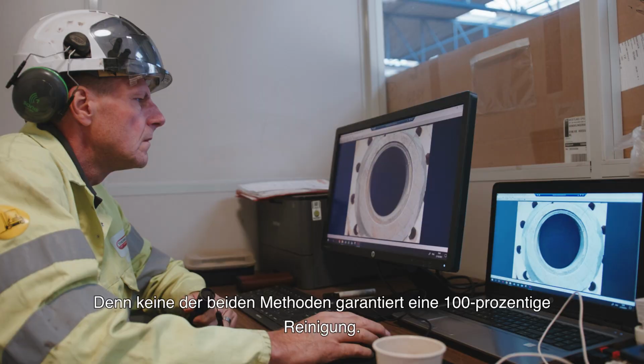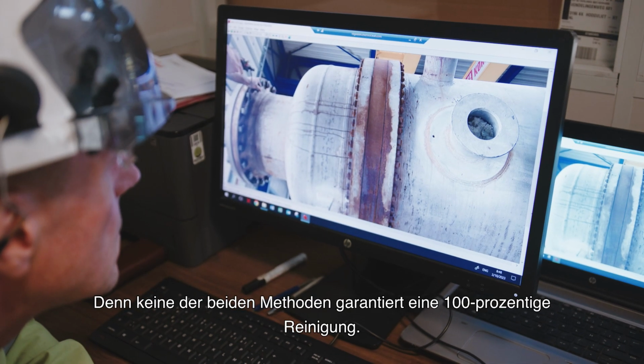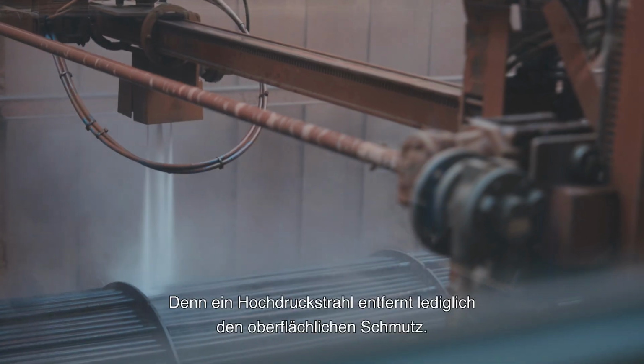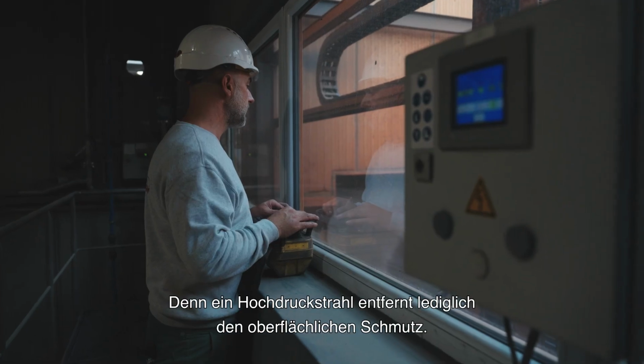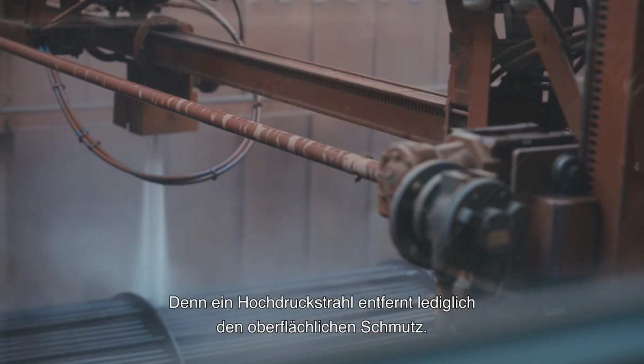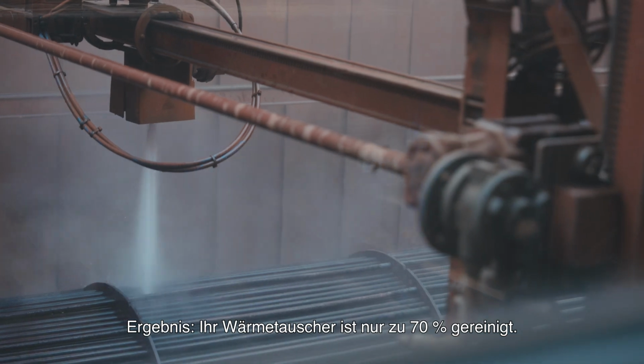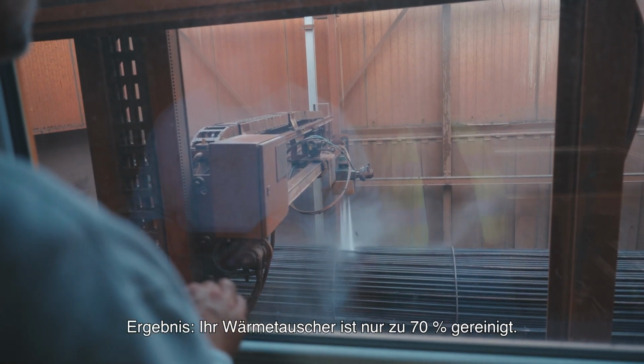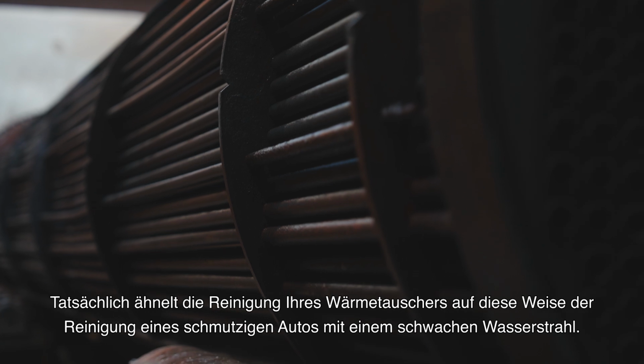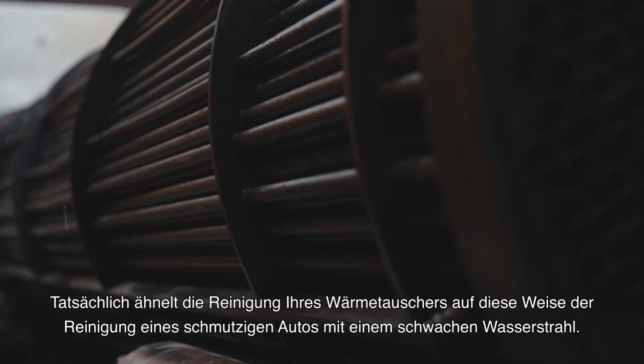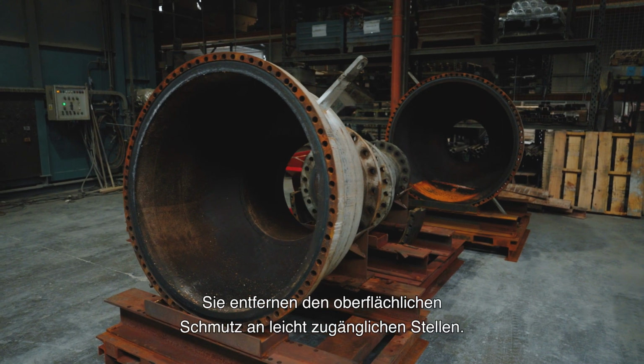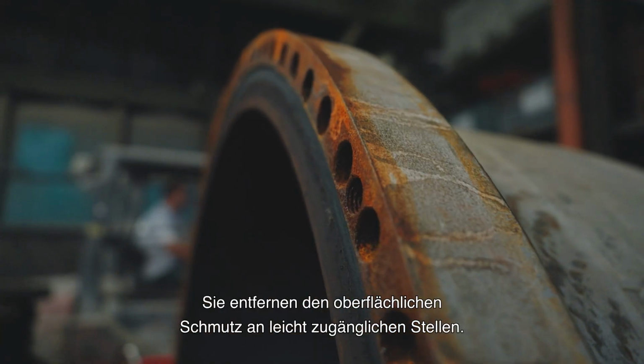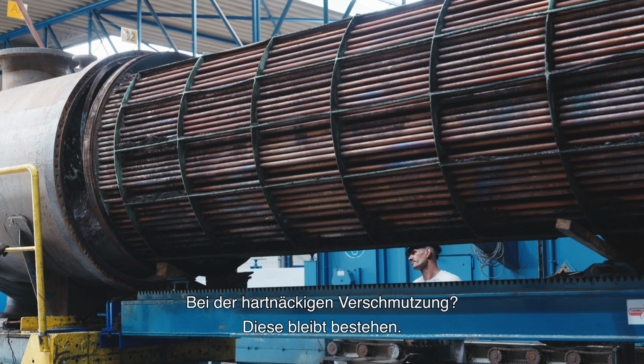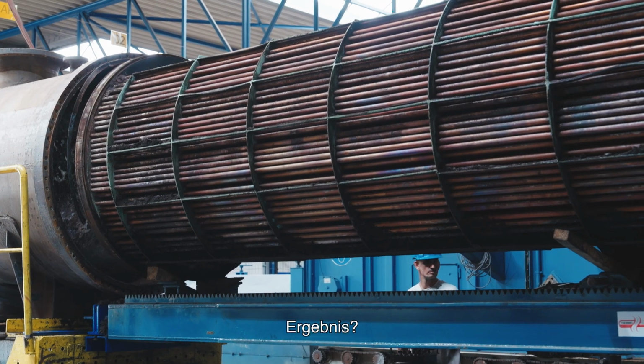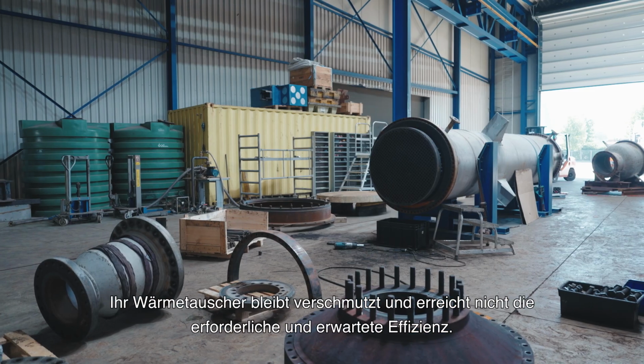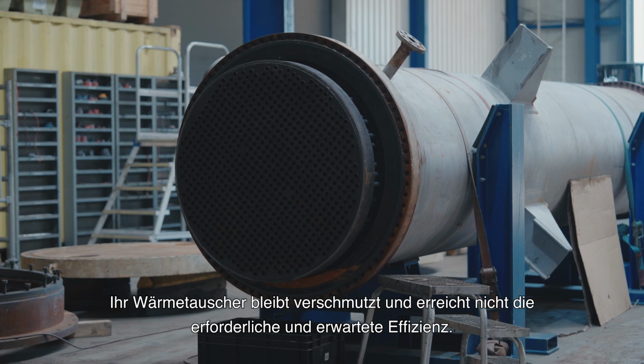Because neither method guarantees a purification of 100%. They simply can't. Because a high-pressure water jet can't reach everywhere and only removes superficial dirt. Result: your heat exchanger is maximum 70% clean. Cleaning your heat exchanger in this way is like cleaning a dirty car with a feeble water jet. You'll be able to remove any superficial dirt that is stuck in easily accessible areas. But those persistent mud stains, they'll still be there. Conclusion: your heat exchanger is still dirty and cannot achieve its specified output.